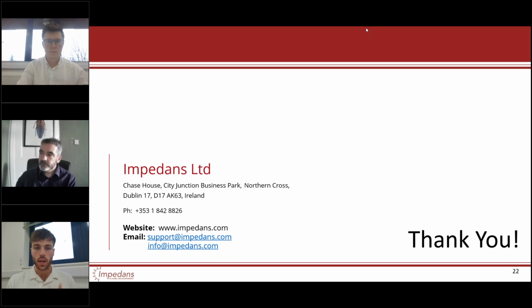Great, thank you very much. And we have another one here. What is the maximum power for the RF inline probe and RF spectrometer, and what are they rated for? So we have a few different options. We have a few different form factors. The highest that we can go to is about 90 kilowatts. So we have some fairly beefy RF sensors that take up to 90 kilowatts.